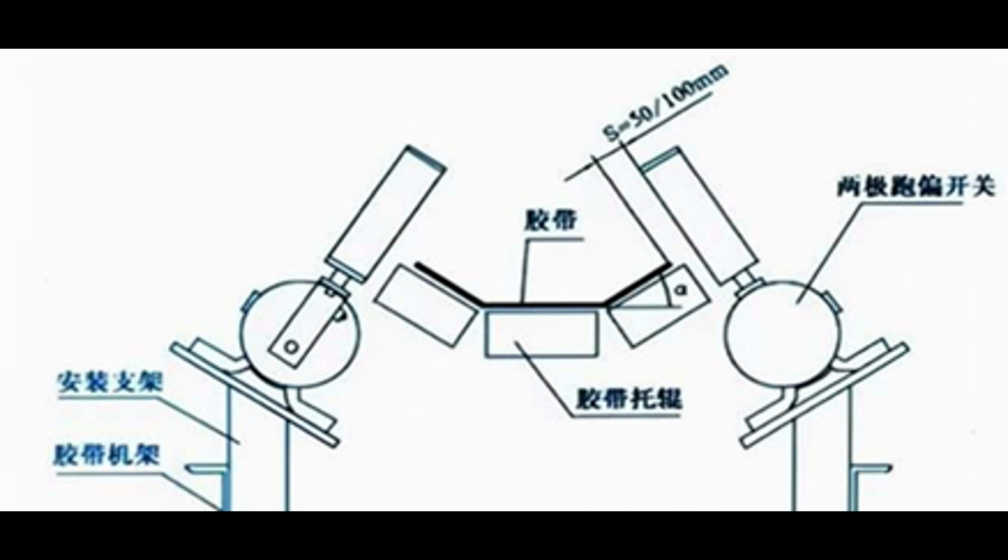The deviation protection of the fixed belt conveyor should be used in pairs, and a group should be installed at the head and tail, and a group should be installed at the variable slope position when the slope of the conveyor changes. A simple deviation protection only needs to be installed at the head of the machine. The anti-deviation device should be fixed on the belt conveyor frame or longitudinal beam with a special bracket. When the running conveyor belt deviates by more than 20 millimeters from the edge of the roller, or more than 70 millimeters for belt conveyors with triple rollers, the anti-deviation device will alarm.